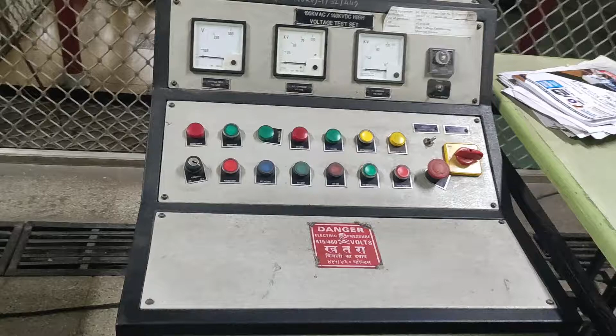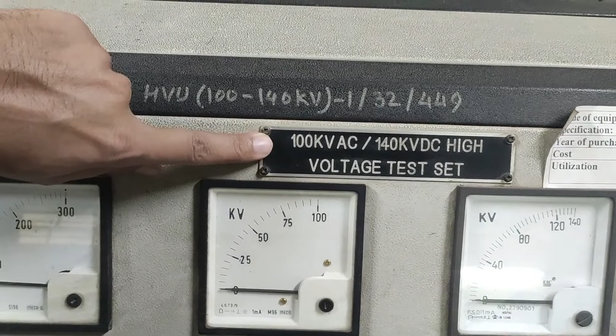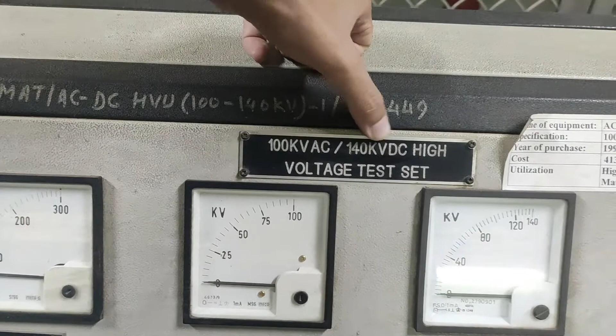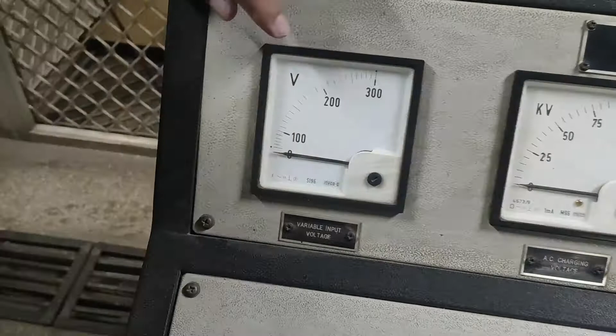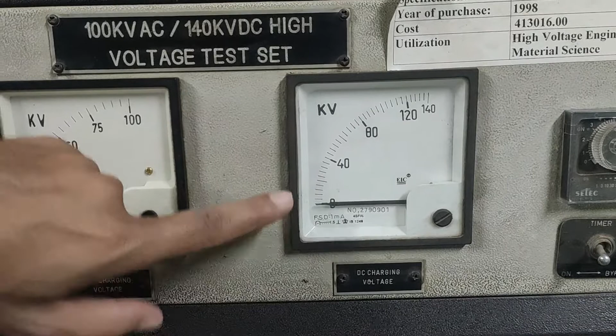So this is another test setup arrangement on which you can clearly observe the 100 kV AC supply. Forget about the DC, because that is for final year practicals. So here we are observing the 100 kV AC supply. Here it is the input voltage which is from 0 to 300 volt. Output voltage which is varying from 0 to 100 kV, and this is the DC from 0 to 140, but we are dealing with the AC supply only.